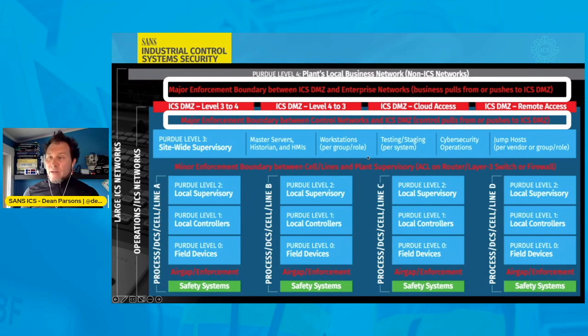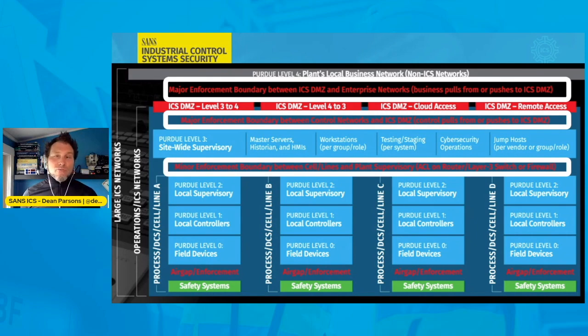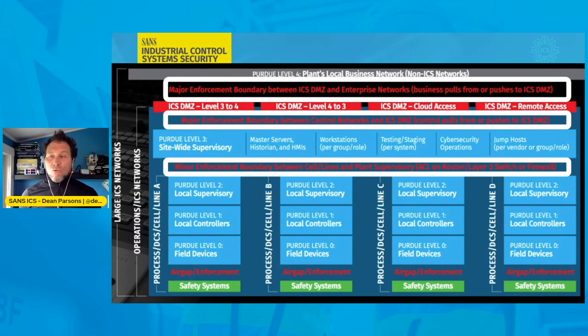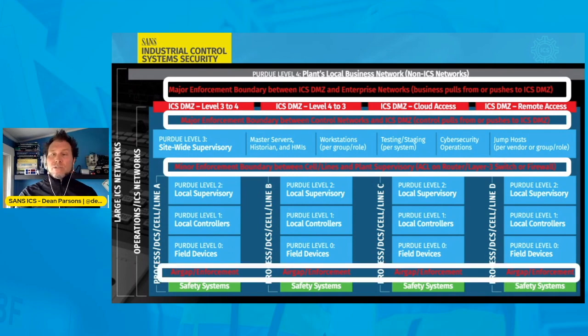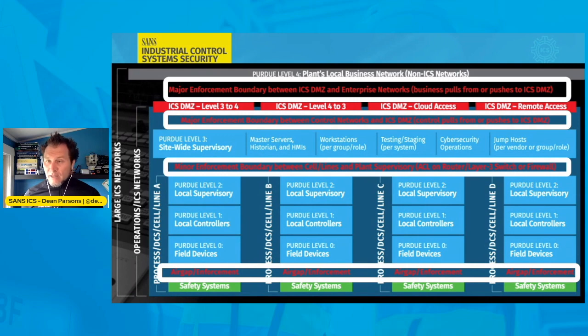Beyond the first enforcement boundary, there is another major enforcement boundary securing traffic between the control network and the ICS DMZ, where the control network pulls from or pushes to the ICS DMZ. There is also an additional enforcement boundary where firewalls, ACLs, ICS-specific switches, and similar controls are applied — looking at traffic between the ICS network and plant supervisory control, using ACLs, routers, layer-three switches, or firewalls. Finally, air-gapping and separating out your safety instrumented systems — using PLCs and actuators to ensure a fail-safe condition — will shut the process down in a regulated way, preserving safety and reliability of people, assets, and the process.